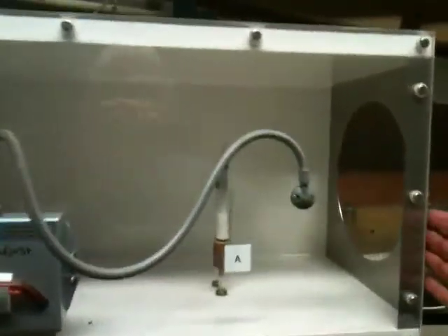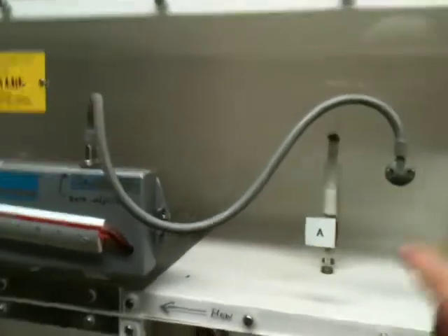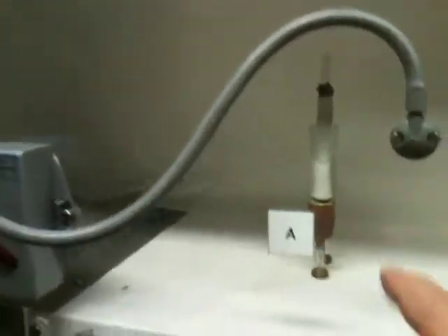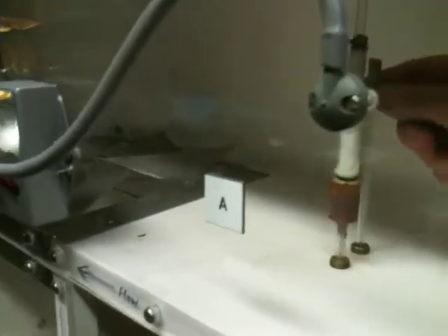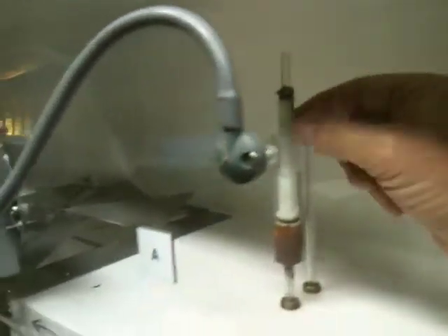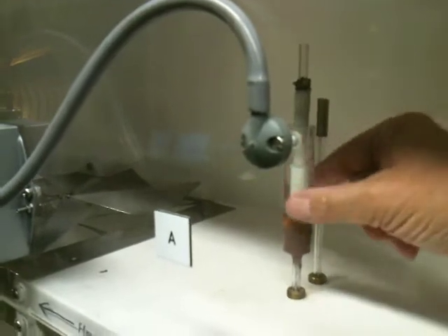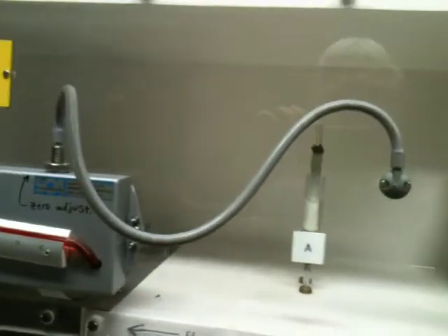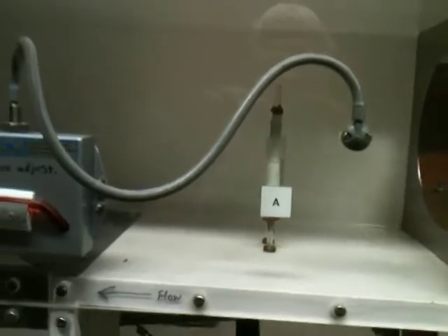So again, here is the inlet, and here is station A. Here is the dry bulb thermocouple, and then the wet bulb thermocouples have wells for water, which we inject through a squirt bottle, and then there's a wick here, just like we have for the sling psychrometer that most of you have used for our previous lab sessions.